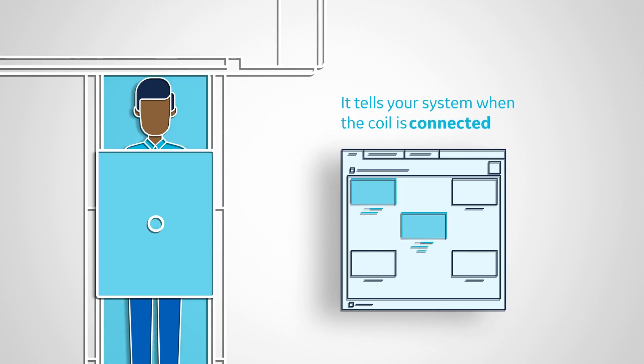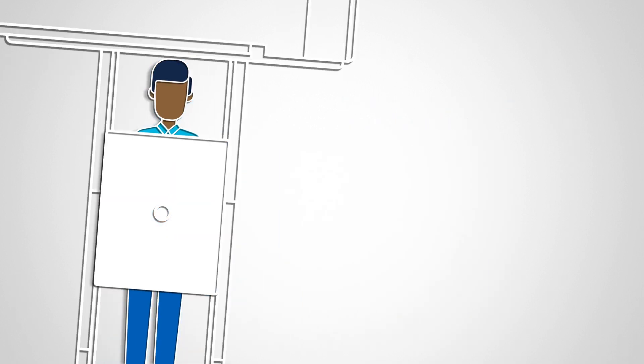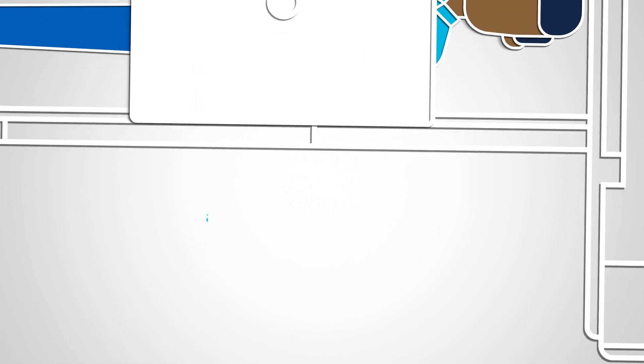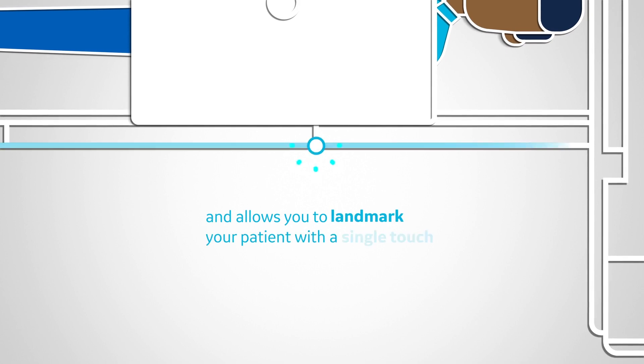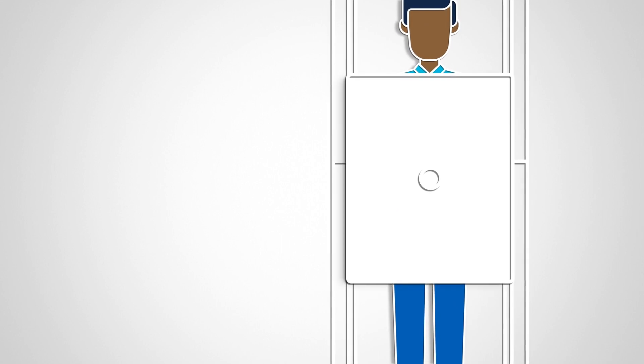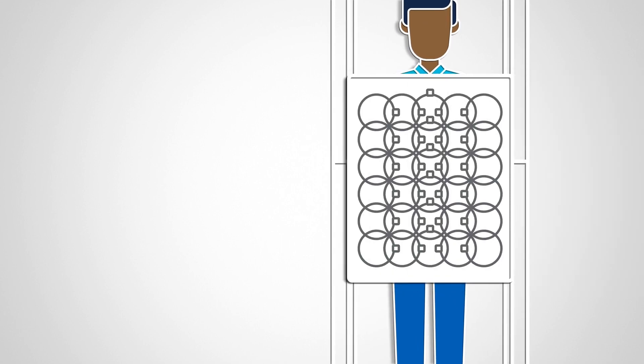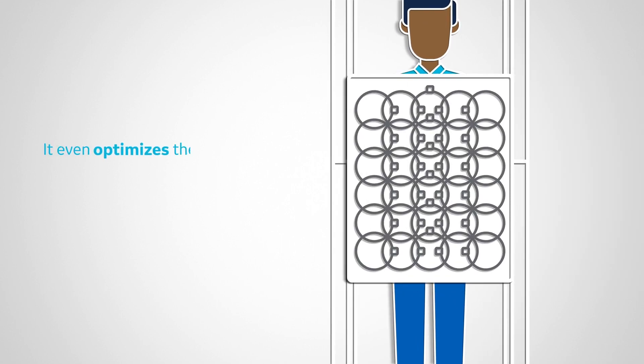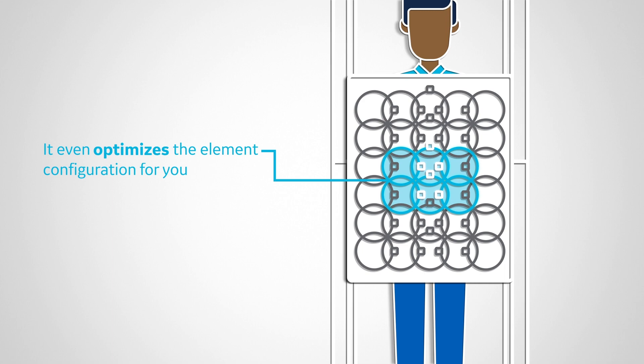It tells your system when the coil is connected and allows you to landmark your patient with a single touch. It even optimizes the element configuration for you.